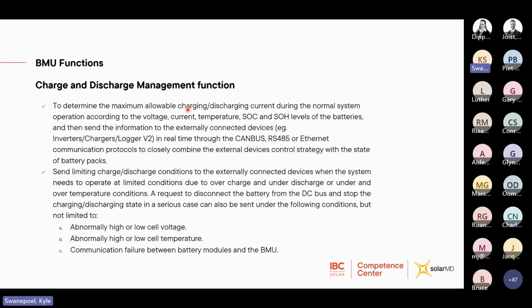So this will be your maximum allowable charge and discharge current for normal operation. And this is based on the voltage, current, temperature, state of charge, and state of health levels of the battery. So there's a lot of factors that need to be taken into account for optimal operation. Any of these not being within optimum range will then cause either a throttled operational step to be given to the inverter, or it will cause a disconnect of the battery from the DC bus. And this information is then sent through to the inverter's chargers and also reported to the logger itself, again via CAN bus, RS485, or Ethernet.